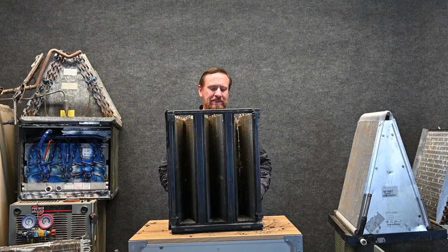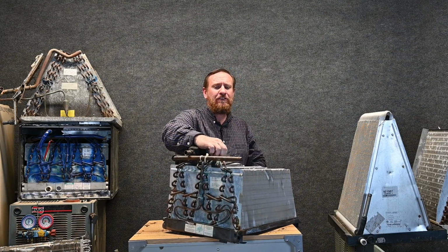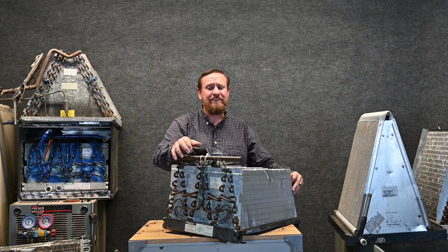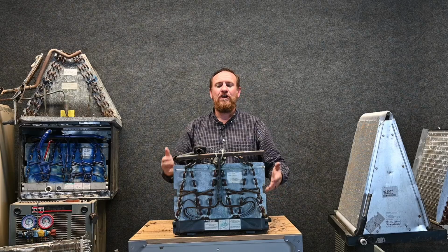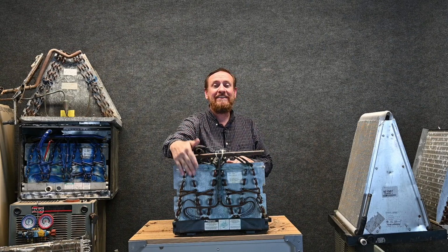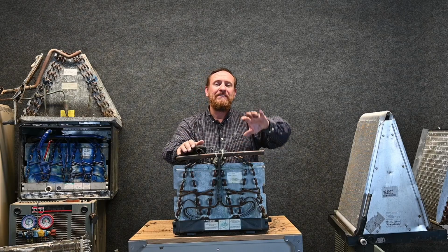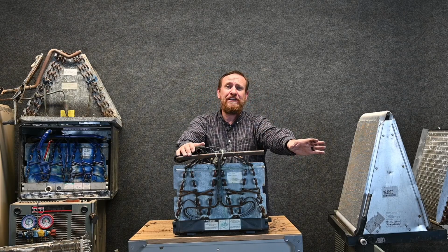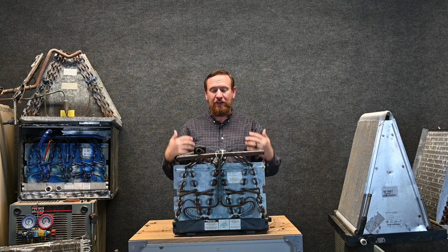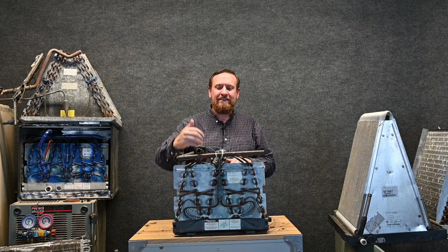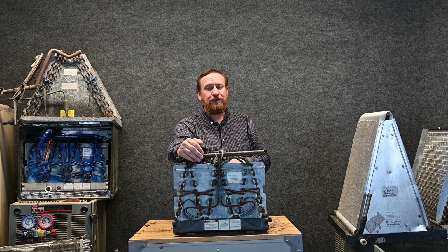And remember, we're going to pull this coil out to clean it, which means we have to take all the refrigerant out of the system. We have to cut our refrigerant lines. We have to cut our drain lines. We have to take this physically out while having these capped off, because we can't let moisture get into these drain lines. And we also have to cap the refrigerant lines because we can't let moisture get in there while we're working on it. We have to clean this with the chemical cleaner and thoroughly rinse this all off, put this back together, rebraze these connections while running nitrogen, and put in a new filter dryer.